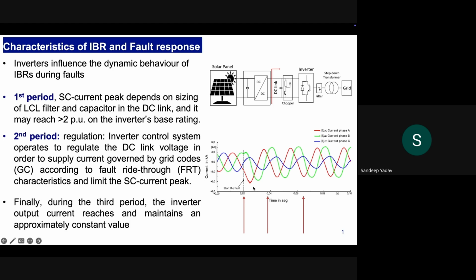Once the controller kicks in, which is the second period, the converter suppresses the negative sequence current and tries to ride through the fault as per the grid code. And the peak current could be slightly lower than the first period, and then the final, which is the third period, where we have only the steady state, and which is, in case of phase to phase fault, mostly positive sequence, and in case of phase to ground fault, it is usually zero sequence at the point of interconnection.